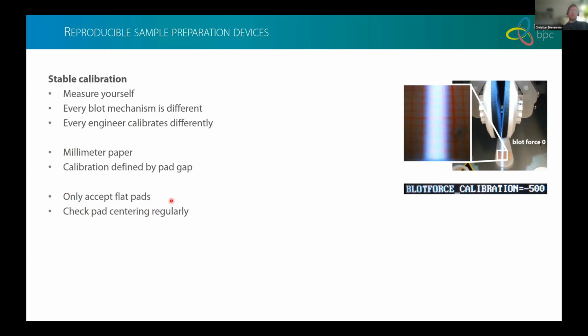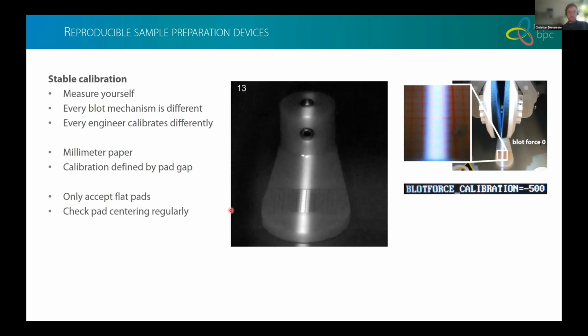And what's the most important for us is that whenever we have any change in the blotting pads, we always check that the pads are flat and they don't have variation. And I will show you a GIF, which is running through the 16 blotting positions twice. And you can see that the width of the light slit actually doesn't change much. So we only accept blotting pads that look like this, because otherwise we get huge amounts of variation.